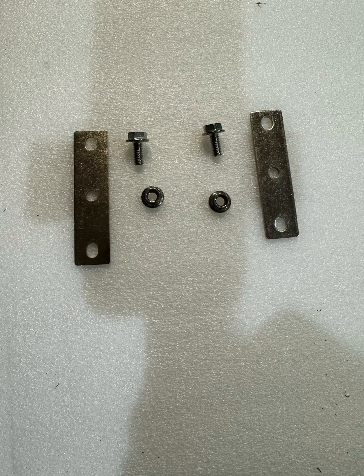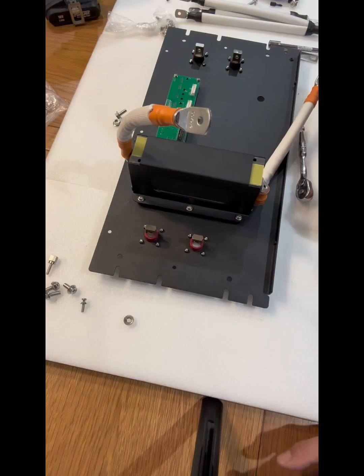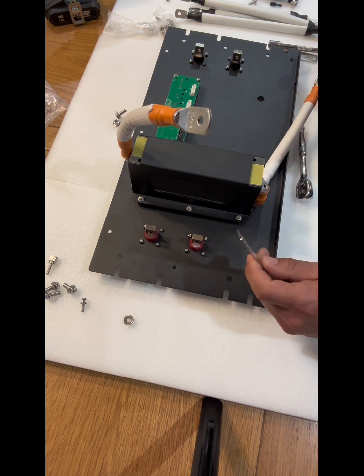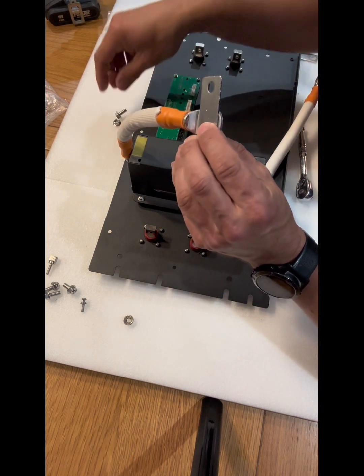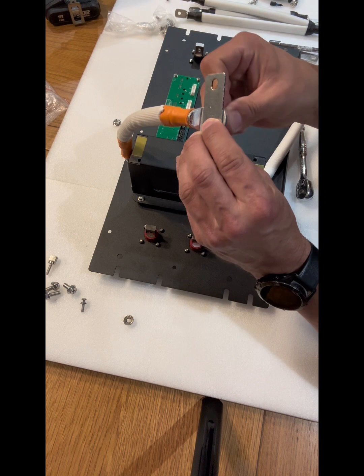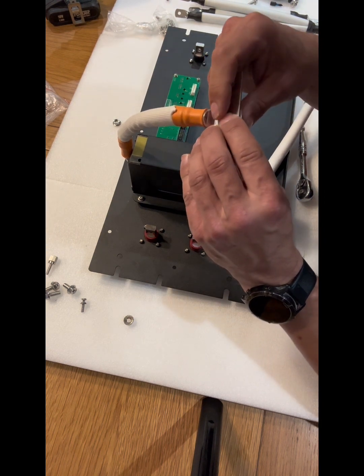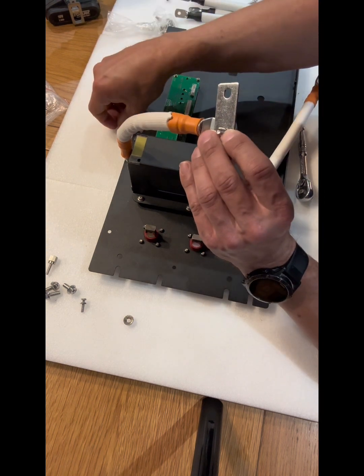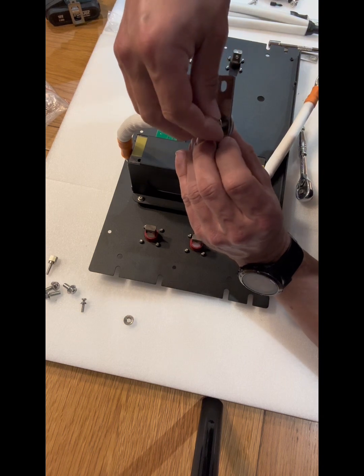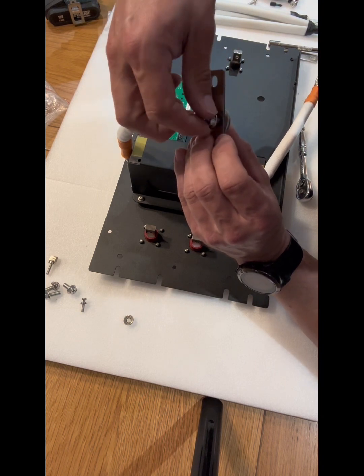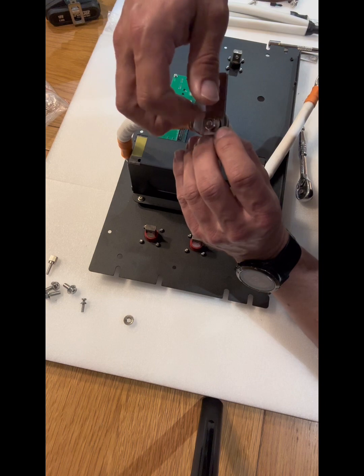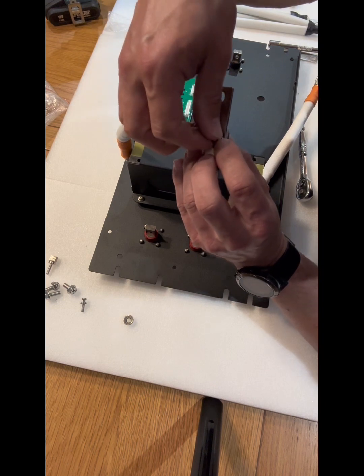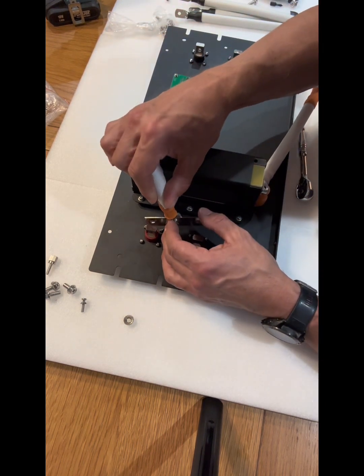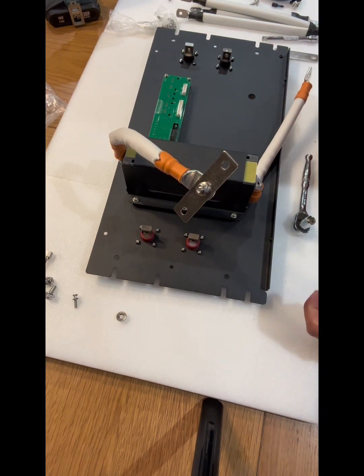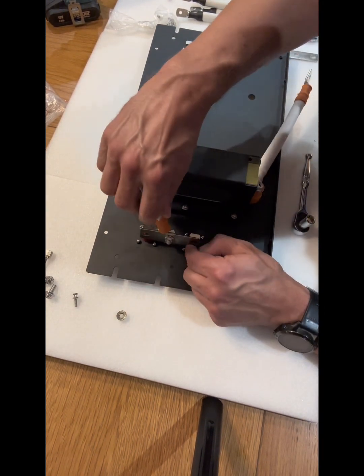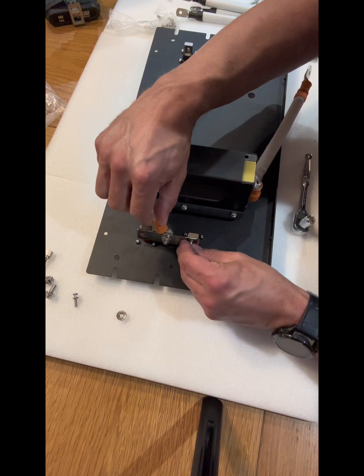You will now find 2 other bus bars in that packet, and this is how they mount. Start with the middle of the bus bar, taking a bolt and the correct nut to mount it right in the middle. Leave it loose before moving it down across the two red terminals. Note it can be mounted on the front or back of the terminals — I chose the front purely because it's easier to access the bolts to screw them in.